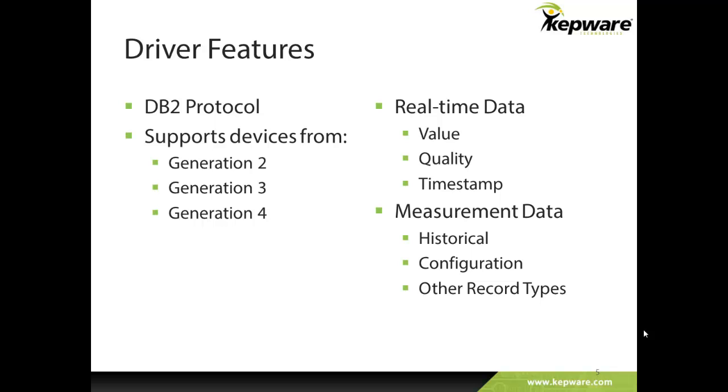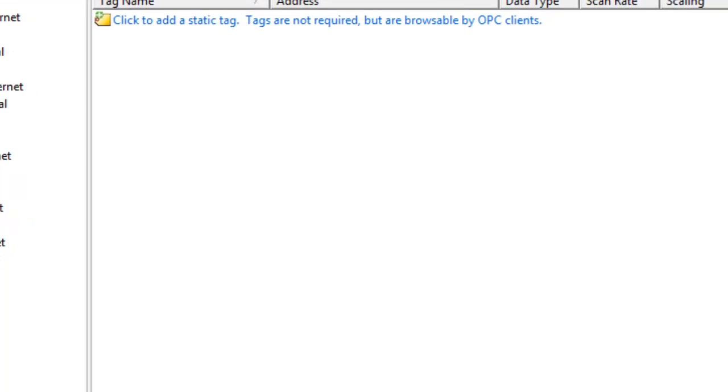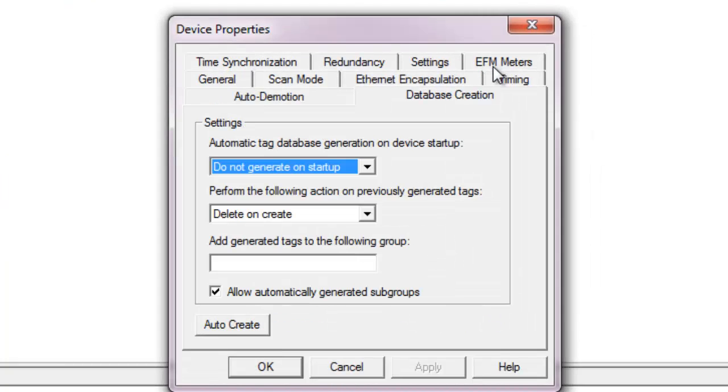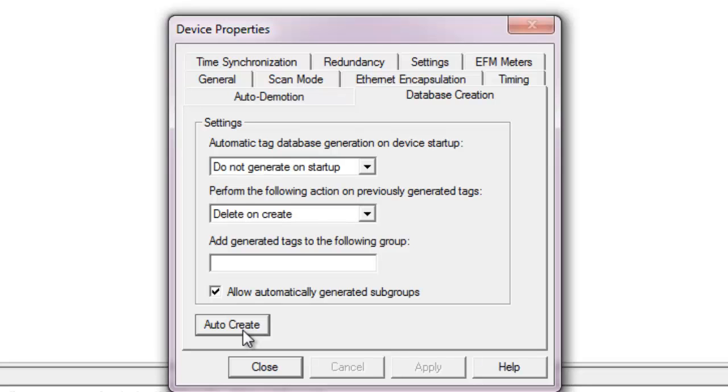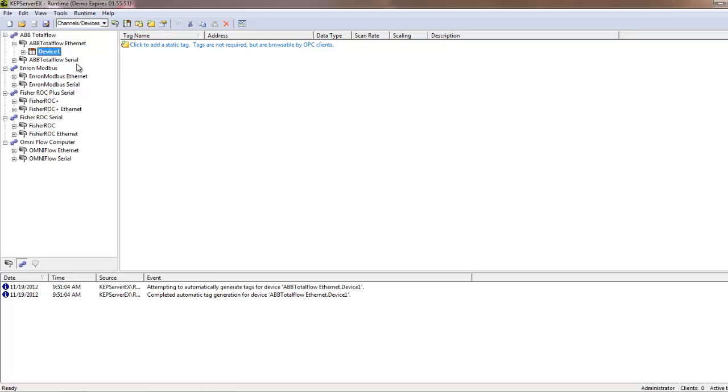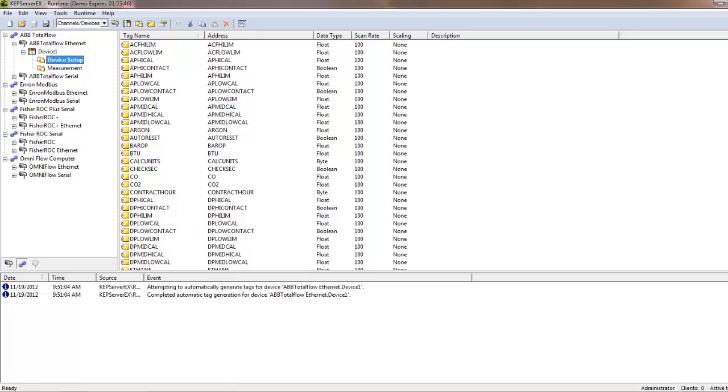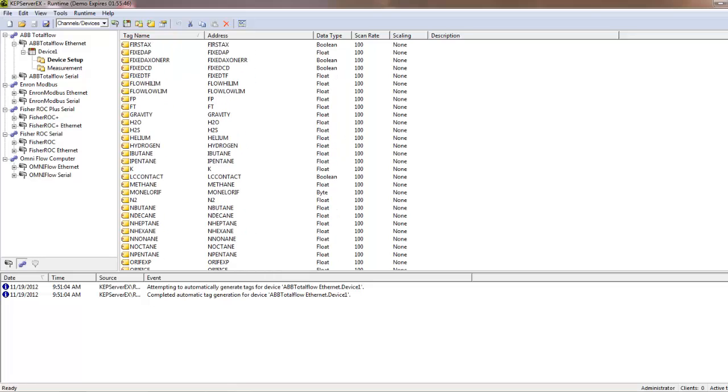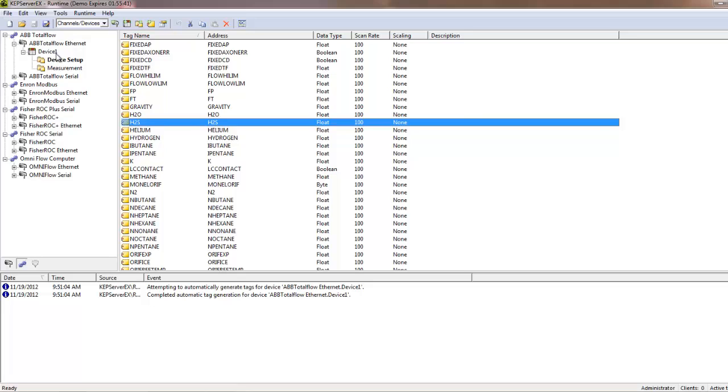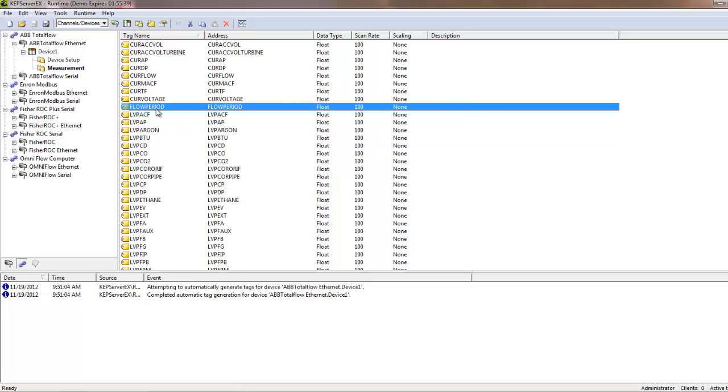Also, registers may be accessed using auto-tag generation. To auto-generate tags, simply go to the Database Creation tab in Device Properties and click Auto-Create. There is no need to import tags from file or be connected to a device to create these tags. Device setup data such as H2S content and measurement information such as flow period are examples of real-time data accessible on the ABB device using the Auto-Tag Generation tool.